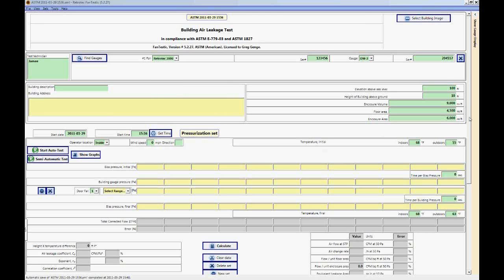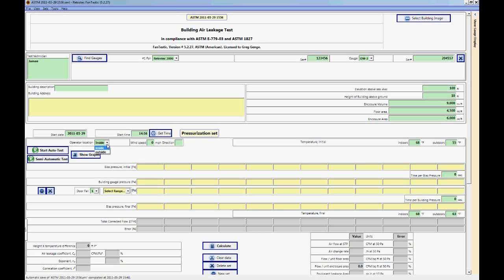So we've already entered the building information including the elevation above sea level, the height of the building, enclosure volume, floor area, and enclosure area. And now we want to select the time that we started the test so we can enter that in manually. Let's say we started it an hour earlier, so 14:36. And when we were doing the test we were inside the building.